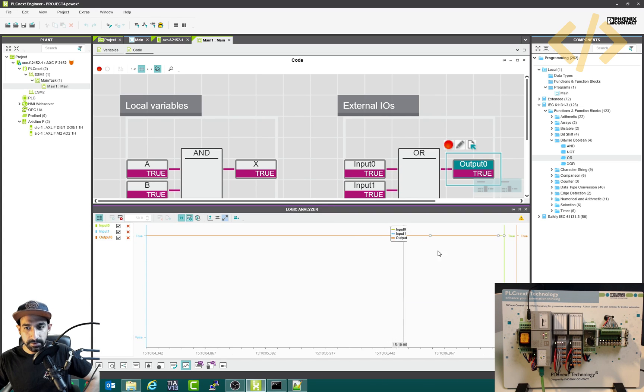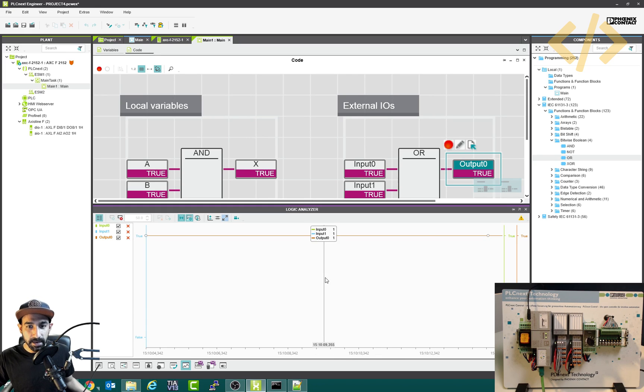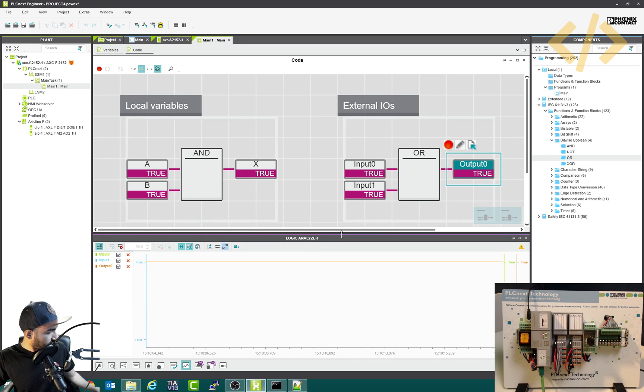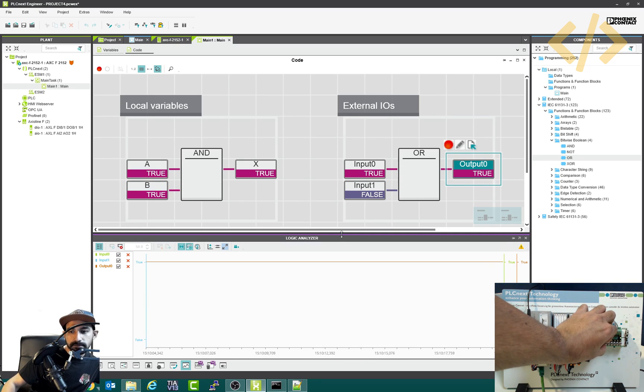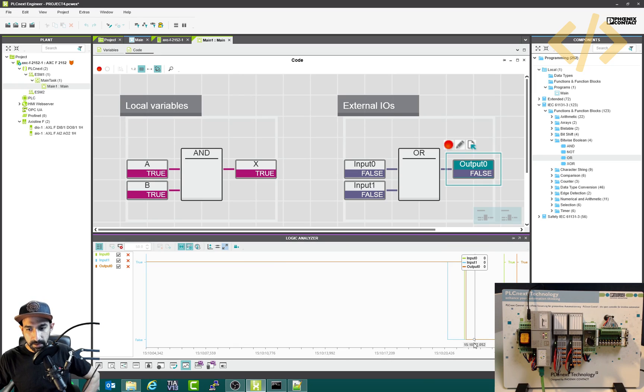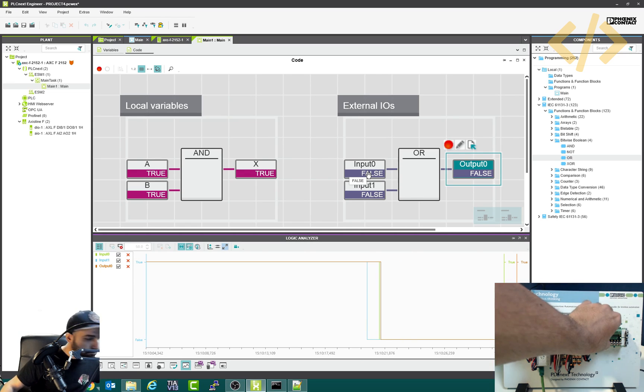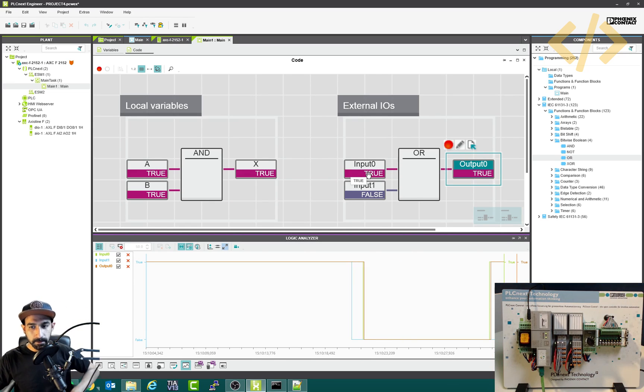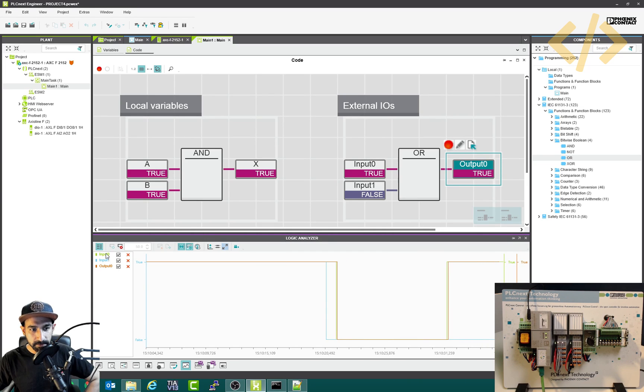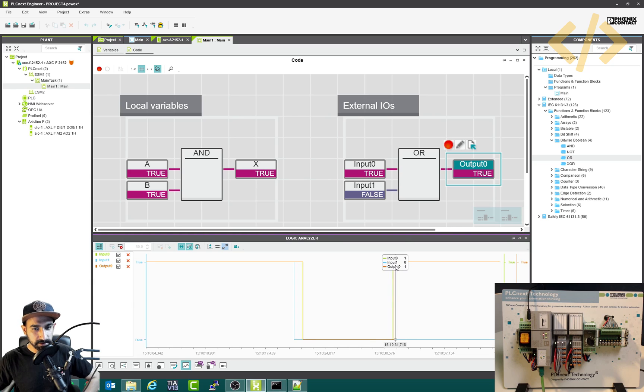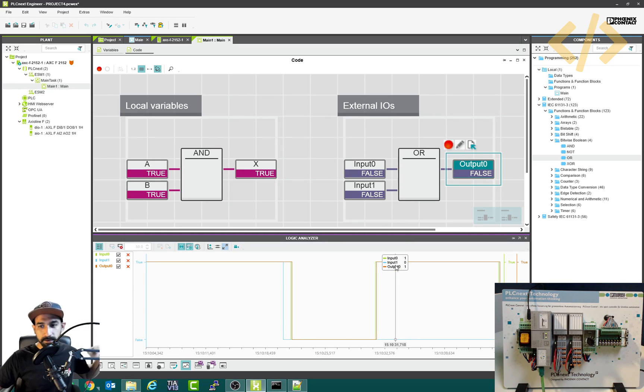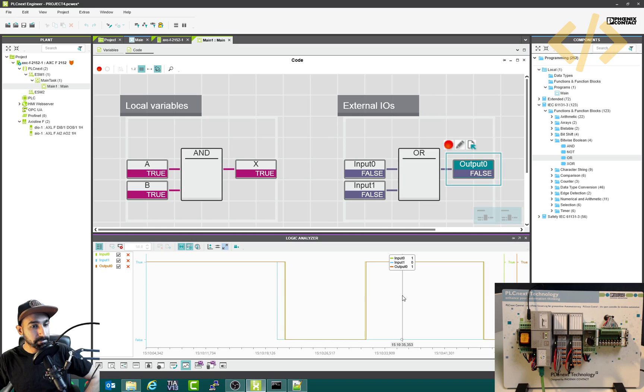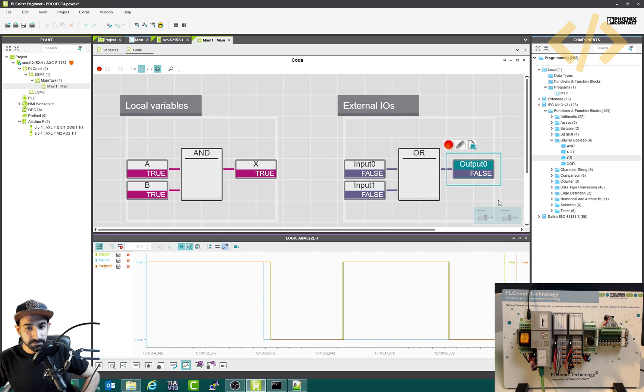So when you do that, maybe I will do it like this, you can see the status of your inputs and status of your outputs in this logic analyzer. It's just a way to monitor the IOs in the PLCnext software. So if I turn it off, you can see the status. So you can see that now this is turned off. So this is a digital pulse. Now I will trigger input zero again. Now my input zero is on, which is the green one. You can see the color from here and output is also on within 100 milliseconds. So this is the input output status you can see here.